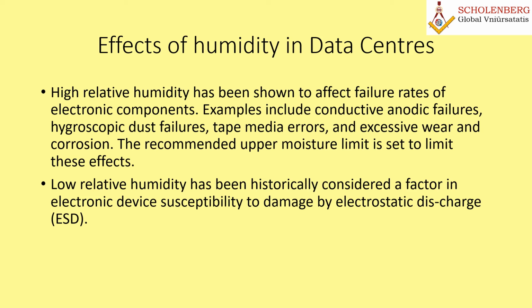This is based on the Pommerenke and Svensson study of 2014, as a result of which the recommended moisture limits have been greatly expanded in these tables, which we have shown just before this slide. The recommended lower moisture limit has been significantly reduced, as you might have seen that we have gone to 8% also in previous tables. Although the static concerns are actually related to relative humidity, the dew point is used because it is fairly constant throughout the data center, whereas relative humidity varies widely. Because dew point can be easily monitored, the dew point of the supply air can be easily monitored, and the return also can be easily monitored and consistently controlled. Best practice is to monitor the moisture content in the data center using dew point rather than relative humidity. This is a very important factor.